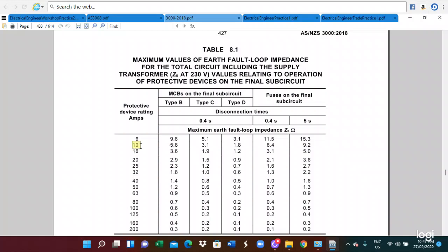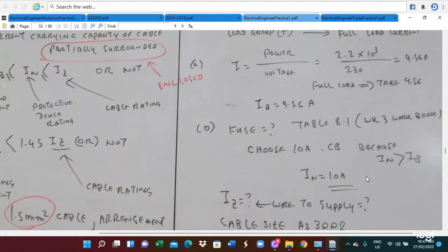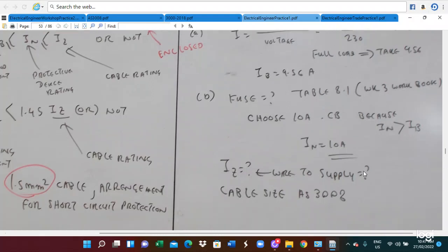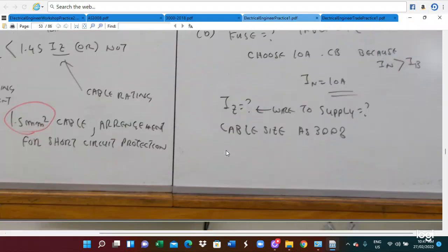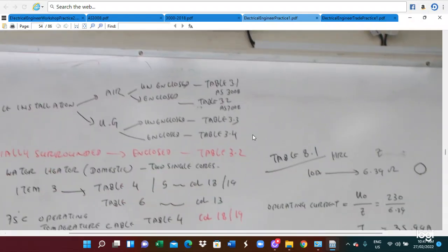We select the 10A fuse rating temporarily. Now we need to find IZ, the cable current-carrying capacity, using AS3008. AS3008 has four installation situations. For cables in air (unenclosed), use Table 3.1. For enclosed cables, use Table 3.2. For underground insulated cables, use Table 3.3. For underground armoured cables, use Table 3.4. Since the cable is partially surrounded by insulation, it is considered enclosed, so we use Table 3.2.